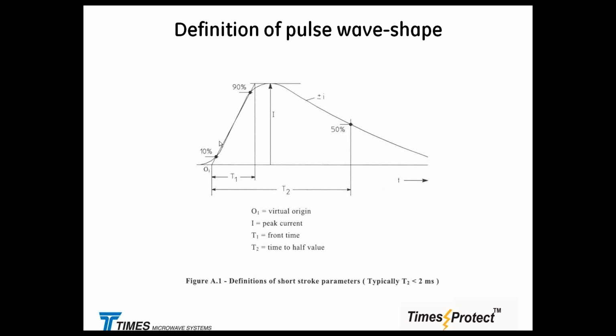So this component will be the frequency component of the event basically. And if you do a Fourier transform and take time to frequency conversion, you're going to be looking at lightning developing frequencies from 1 up to 10, 15 megahertz. So for all of us working in broadband wireless or microwave, that's not really that high. But that frequency basically is going to play some tricks on any conductor, which will be an inductor suspended in the air. The other value for that current will be the pulse duration. How long does it last? So we always measure the pulse duration of the 20 microsecond or 30 or 40 or 50 at the 50% of the rate of the rise time. So this is the RF component, this is the DC component. If you integrate this area under the curve, you see the total amount of charge coming down on you in terms of electromagnetic field.